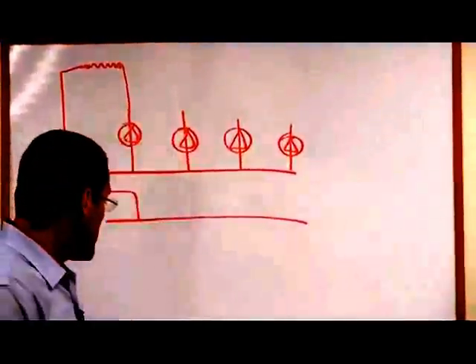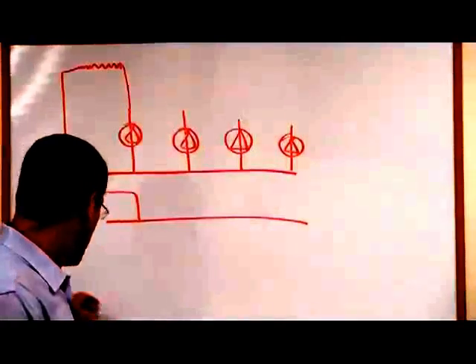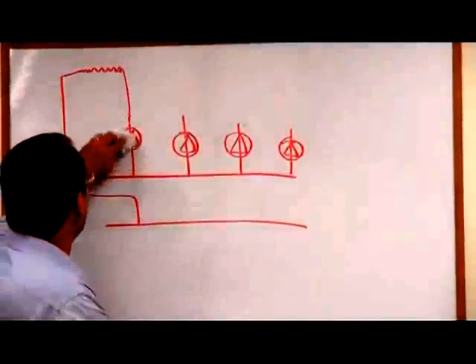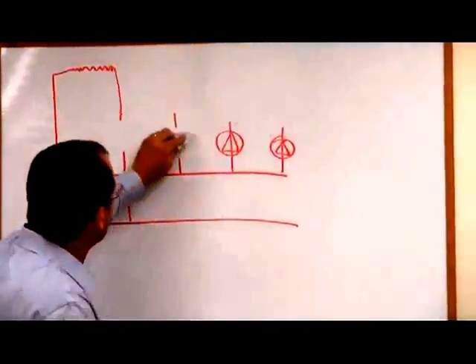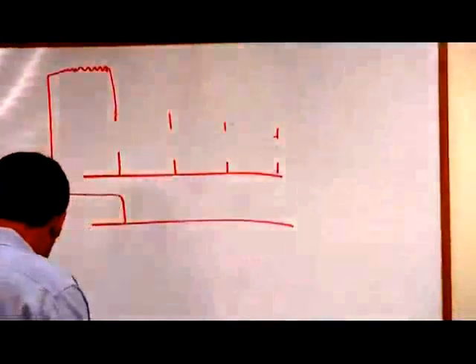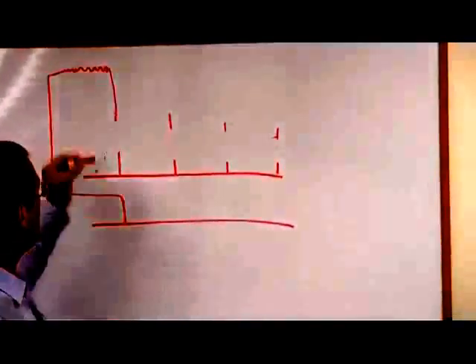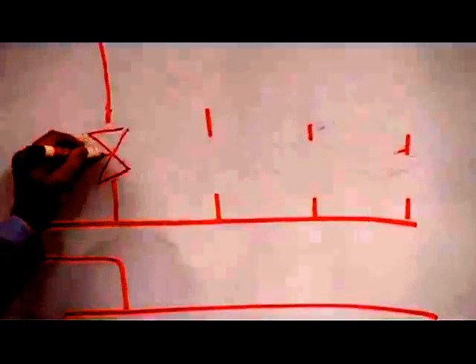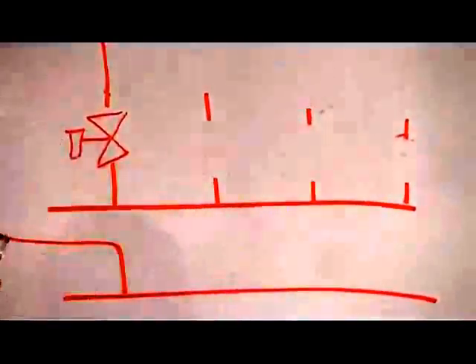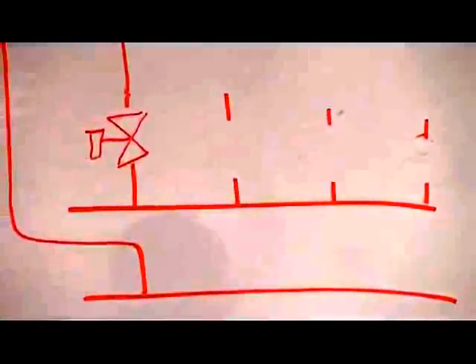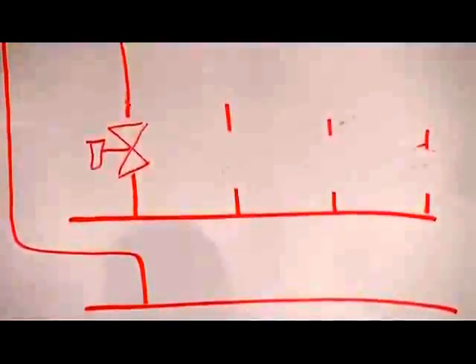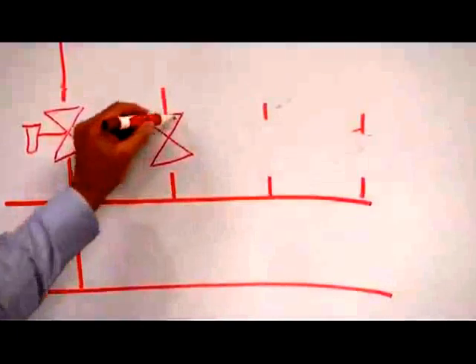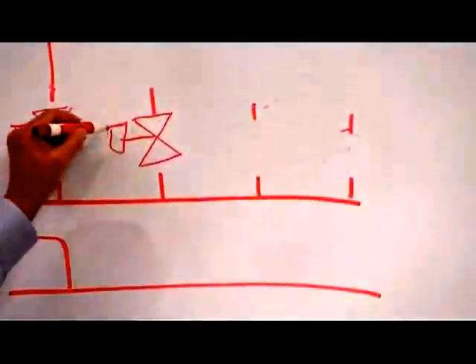The new technology we're going to talk about takes a single pump and we replace all of the other pumps with a low voltage device that's called a zone valve. And all the zone valve does, instead of using 110 volts, it uses 24 volts and just opens and closes. So those pumps get replaced by this small low voltage device called a zone valve.